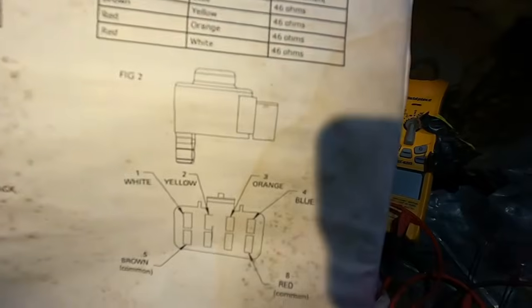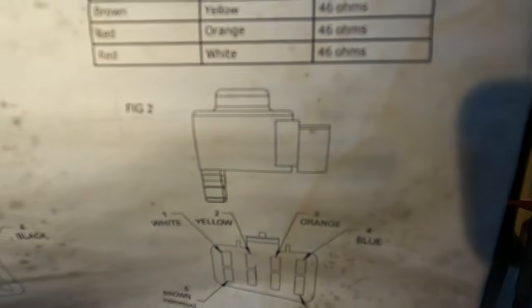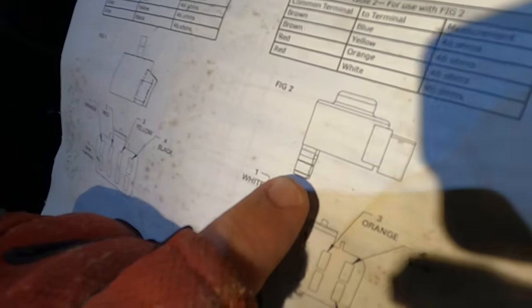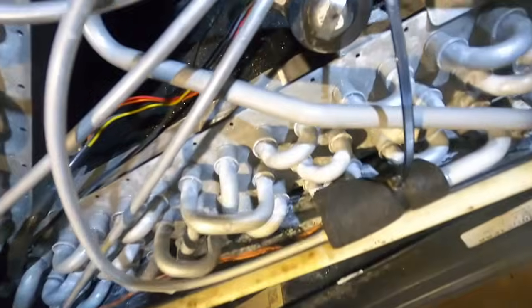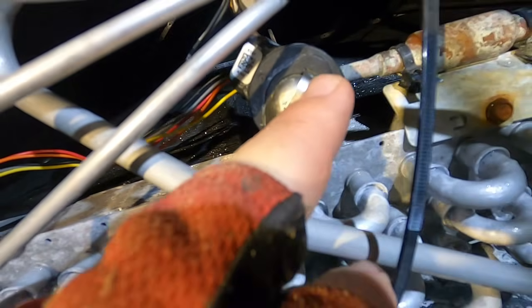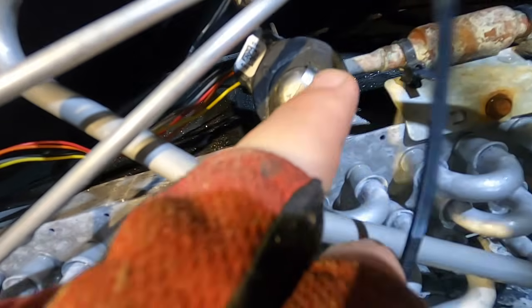You've got your bottom clip stepper motor, and this is the one that's on the outdoor unit, and it clips to the line that the EEV is mounted to, and that's what holds it in place. Air handlers have these. You've got a metal top strap, and the end of this EEV has little divots in it, and then you've got impressions on each side of this metal clip, and once you get it on, you just turn it until it snaps into place.